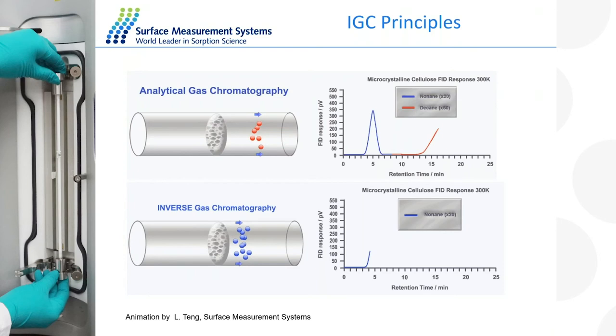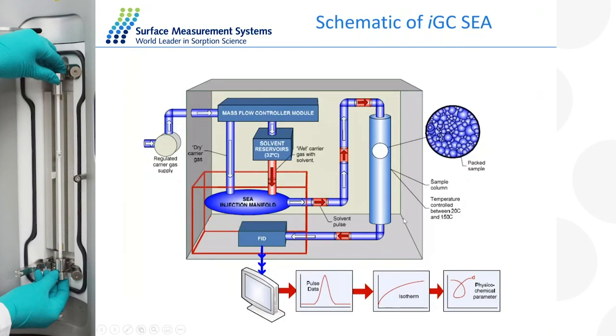Describing the instrument setup in more detail: the column is packed with your powders, fibres, or films. Like any normal gas chromatograph, we use a helium or nitrogen carrier gas passing through the column. We inject different gas-phase species — hydrocarbons like octane or decane, alcohols like methanol or ethanol, or more acidic samples such as acetic acid or basic materials like amines. A flame ionisation detector at the end measures the time of flight — how long it takes for the molecules to pass through the column — and from the chromatographic data an isotherm and then a physiochemical property is obtained.